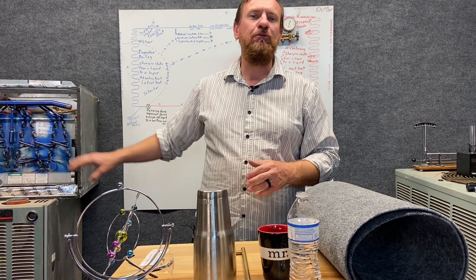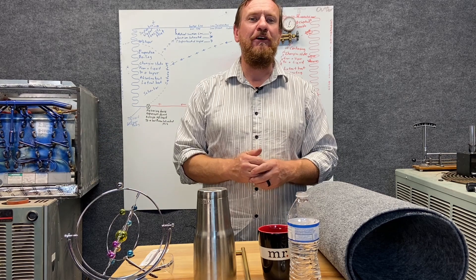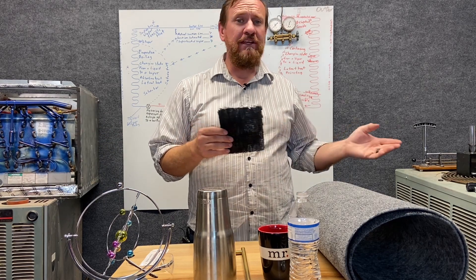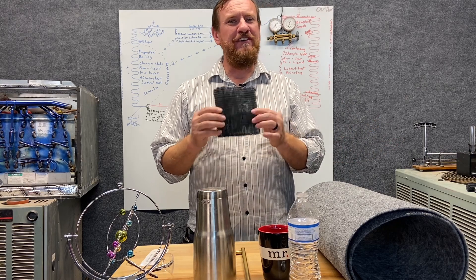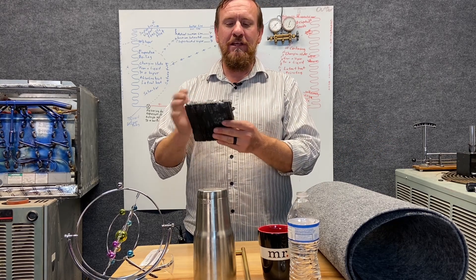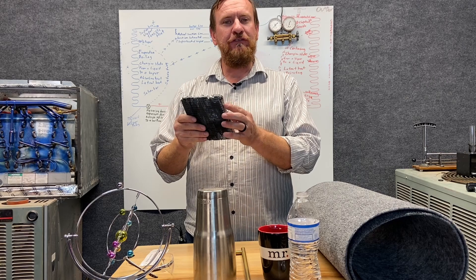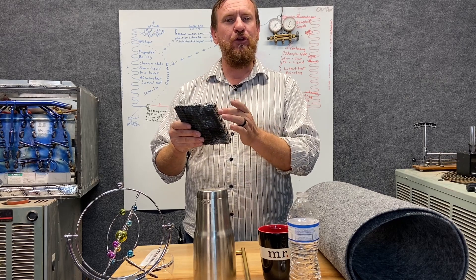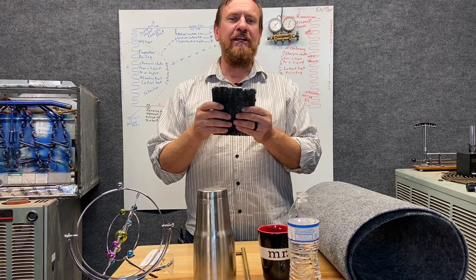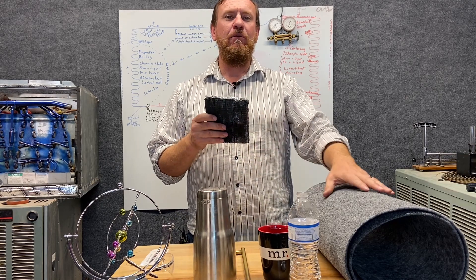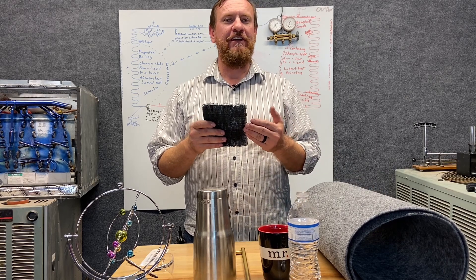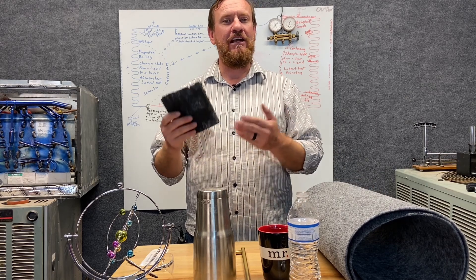This is why in the indoor coils we're going to use a type of aluminum fin. The metal we use in the evaporator coil or the condensing coil is very important. The refrigerants are low temperature inside and the air is warmer. The metal transfers heat from the warmer air to the cooler refrigerant very effectively, just like when I'm touching this. Now if this evaporator gets dirty, we end up putting dirt on it — it works like an insulator and we don't transfer heat very effectively, which causes a problem.